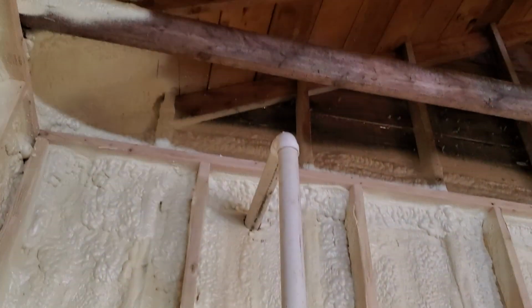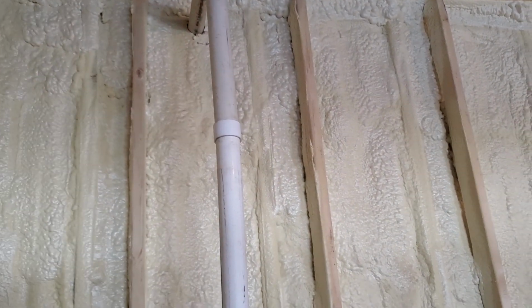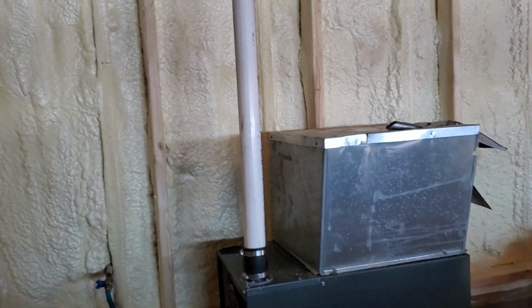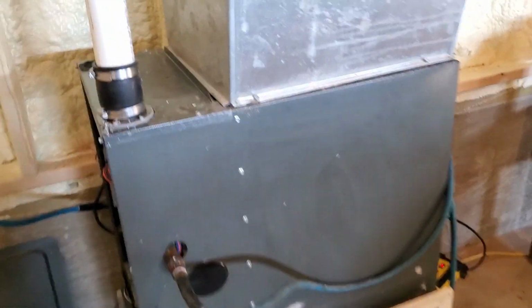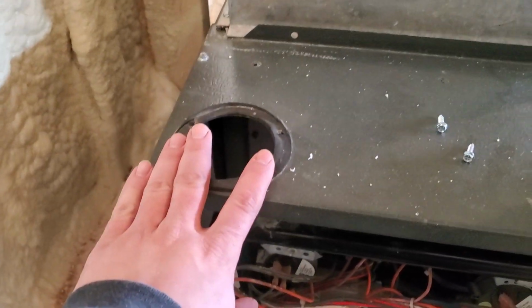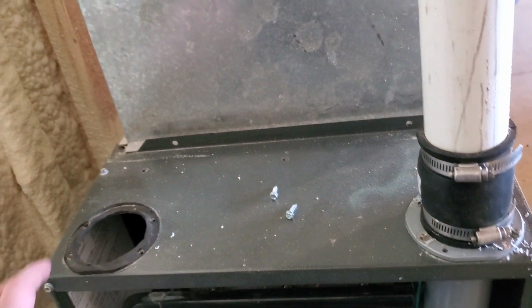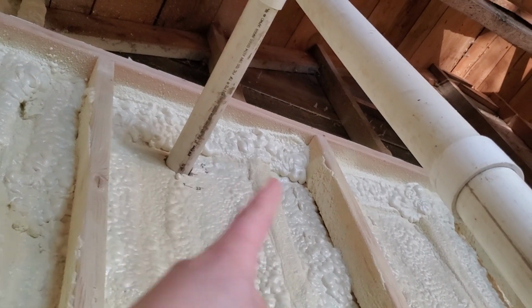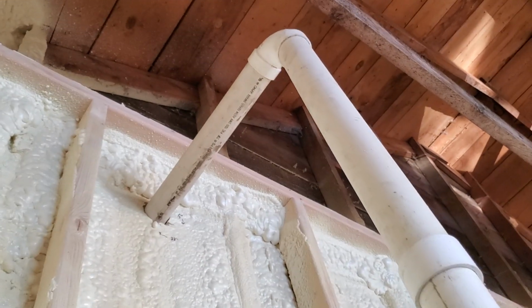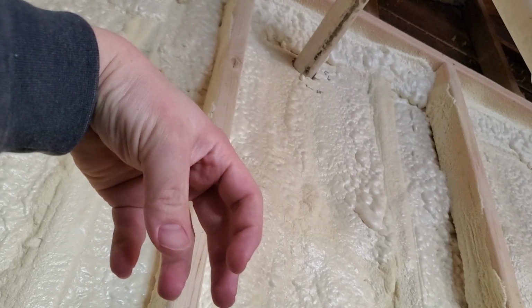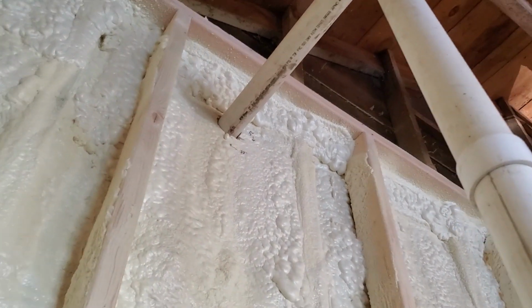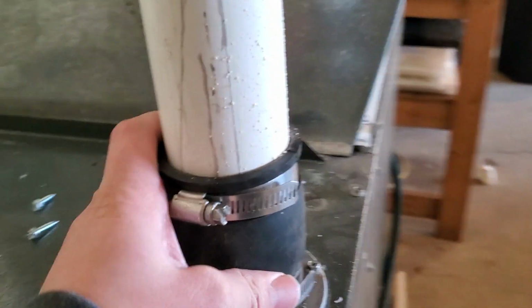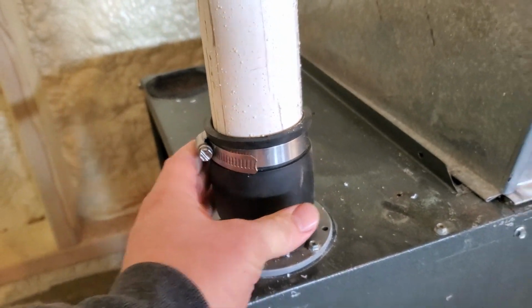Now, depending on what you're using the furnace for, you can use either one or two vent pipes. In this case, we're just using one. We weren't doing anything in here that was extremely dusty. We're not doing drywall or anything. If you're going to be doing drywall and you want a temporary furnace, you should probably run your second pipe for a direct vent furnace setup. So we just run a second 2-inch PVC pipe up and out next to the first one, about a foot over or so. It can even be a little bit closer and it'd be fine. Just put an elbow on the intake facing down, and your exhaust can just go straight out. It's oftentimes helpful to have a couple of Fernco or flexible rubber couplings to connect your vent going up and out. That gives you the option of disassembling it if you need to move it again.